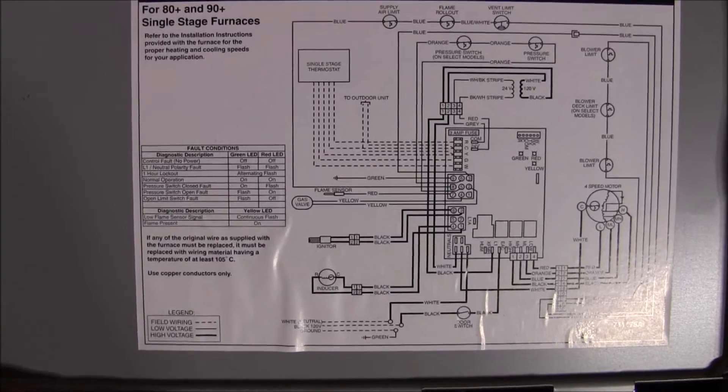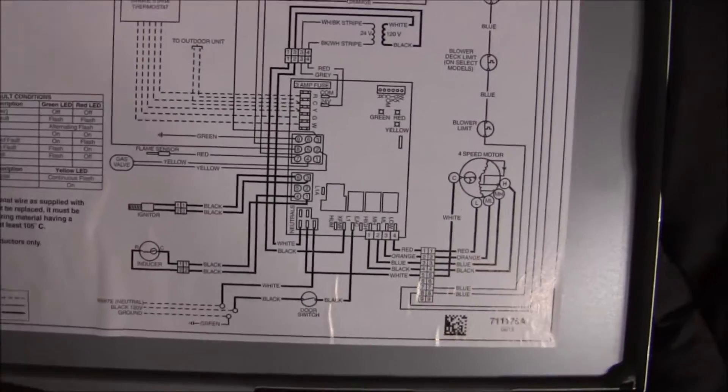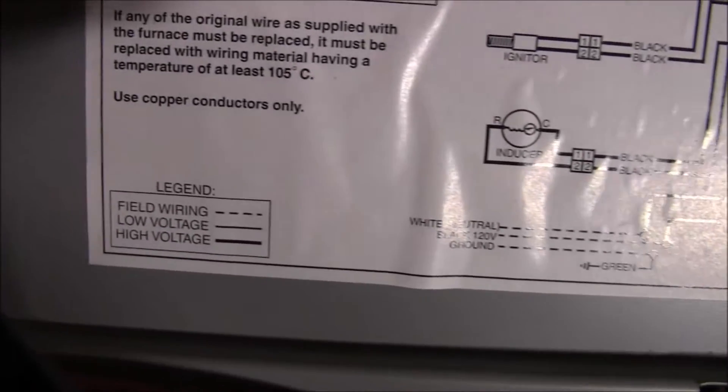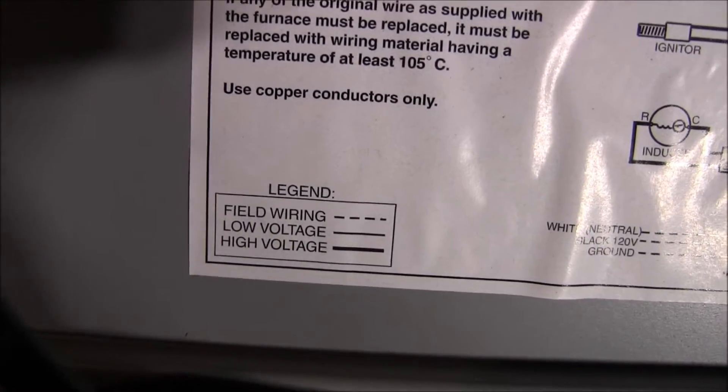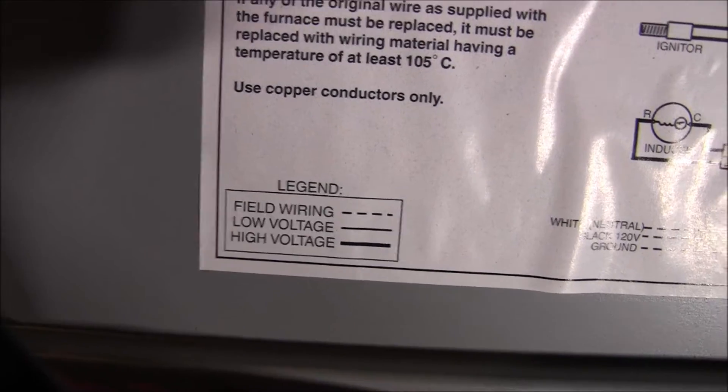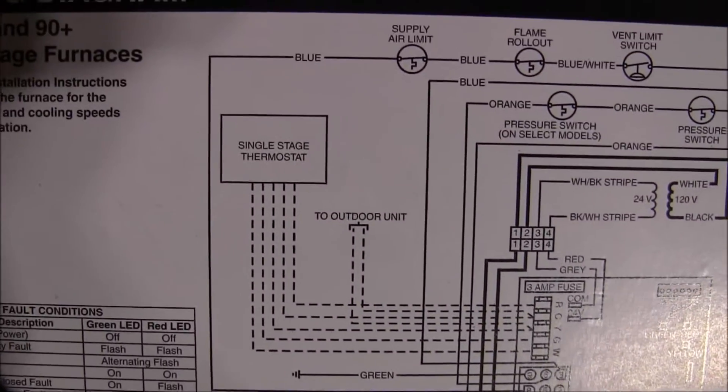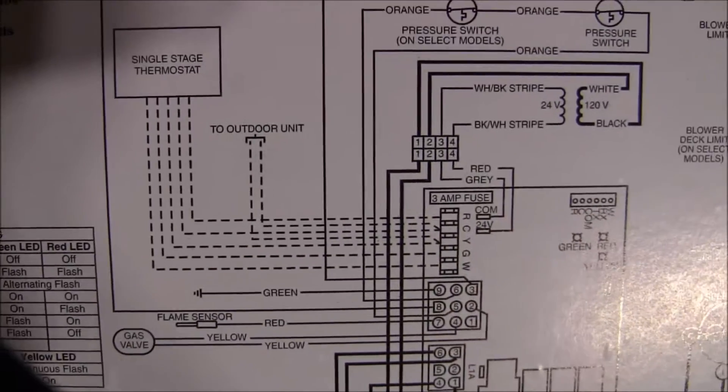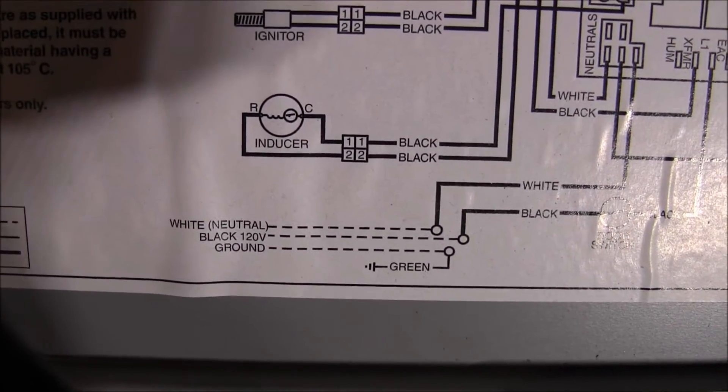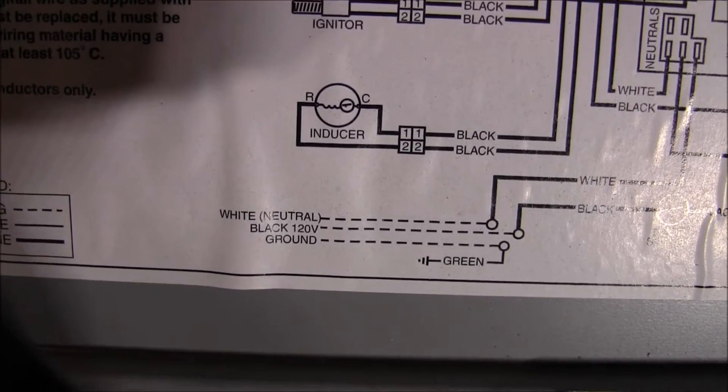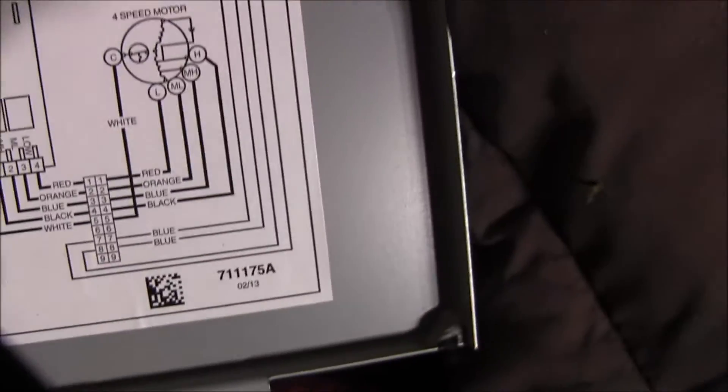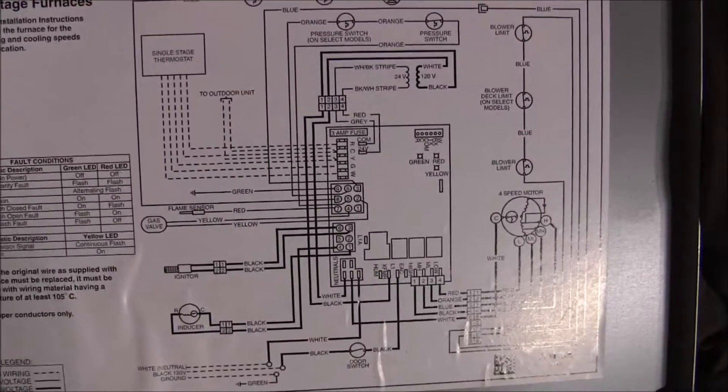So today we're going to install what's called the field wiring. If we look really close at the little legend down here in the corner, the field wiring is the dotted line. The dotted line consists of the low voltage side, which is from the thermostat down to the control board, and also the connections from our house supply: 120 volts, white, black, and ground that you see at the bottom of the schematic. The rest of this is all diagnostic stuff, which we don't have to get really involved in.